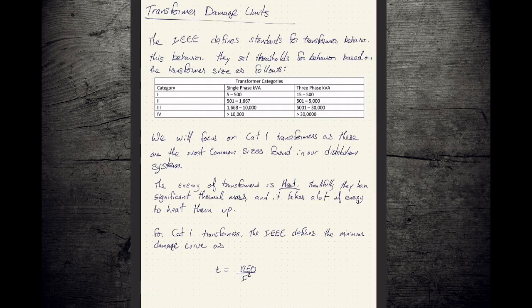And again, it's back to standards. It's the IEEE. So in Canada, we use an IEEE standard for transformers. We liked it a lot, so we put a Canadian Standards Association number on it, and it's the same thing. And we divide our transformers into categories. And we're going to focus in this class on category 1 transformers because, 5 to 500 kVA single phase or 15 to 500 kVA on a three phase, that covers the lion's share of your pole mount.